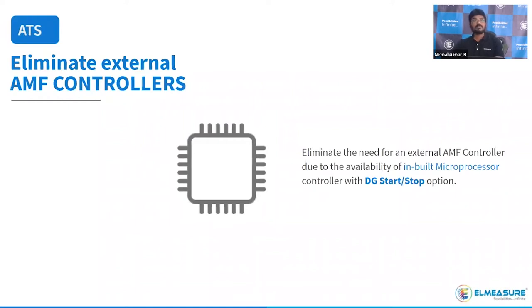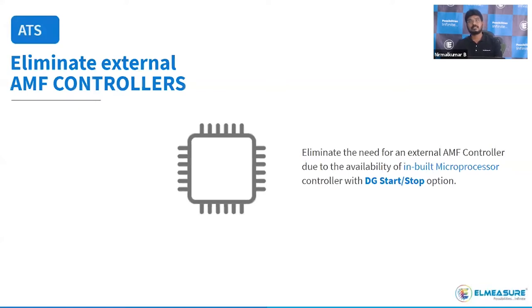The benefit of using Elmeasure ATS is the in-built microprocessor-based controller — the customer has no need for any external controller. Competitors like ABB, Socomec, and L&T provide only the mechanical parts, called remotely operated ATS, and require a separate ATS controller. In Elmeasure, there is no need for any external AMF controller or external accessories, whereas panel builders normally need an ATS controller, line voltage monitoring relay, and external on-delay timers.